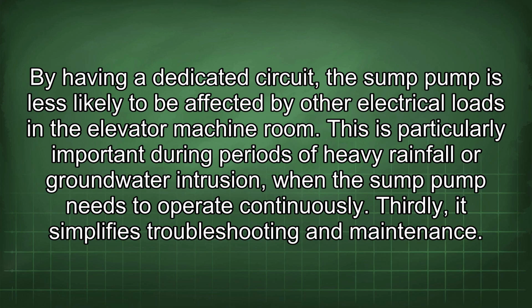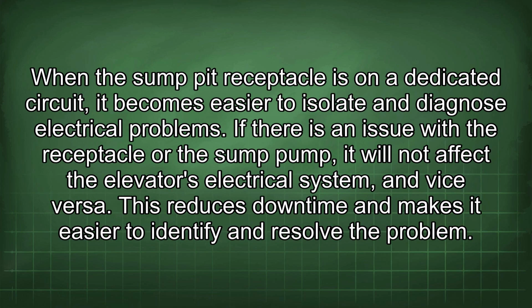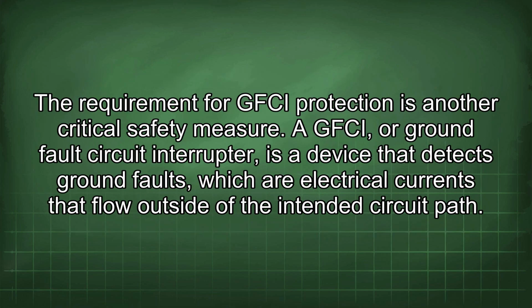Thirdly, it simplifies troubleshooting and maintenance. When the sump pit receptacle is on a dedicated circuit, it becomes easier to isolate and diagnose electrical problems. If there is an issue with the receptacle or the sump pump, it will not affect the elevator's electrical system, and vice versa. This reduces downtime and makes it easier to identify and resolve the problem. The requirement for GFCI protection is another critical safety measure.